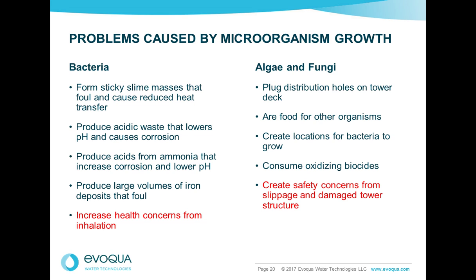Problems caused by microbiological growth. Bacteria can form a sticky, slimy mass that fouls the cooling effects. It'll cause short-circuiting within the system. It can plug a heat exchanger. Again, you could wind up producing acid from ammonia. You get iron-depositing bacteria, which can foul the system. I mentioned fungus can eat the cooling tower wood and create food for other bacteria.